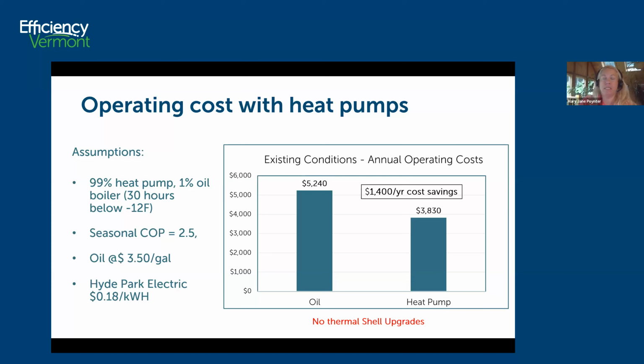So let's make the basic assumption that 99% of all of the heating oil has been offset by heat pumps, and the oil boiler is still used 1% of the time for those really cold temperatures. The calculations were done at $3.50 a gallon for oil and 18 cents a kilowatt hour for Hyde Park. All you do is put in heat pumps, you're already saving $1,400 a year just in operating costs. Now, if the cost of oil went back down to $2 a gallon, that cost savings is really going to shrink.